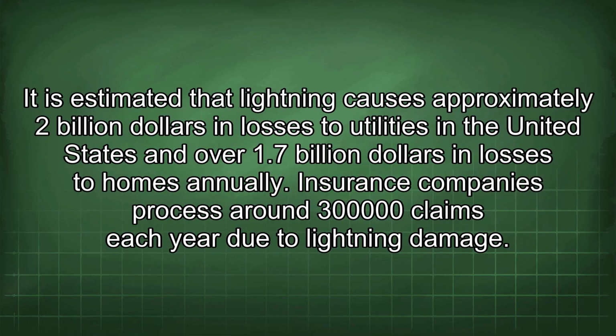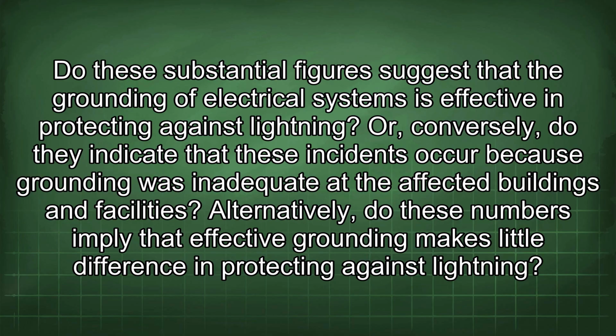It is estimated that lightning causes approximately $2 billion in losses to utilities in the United States and over $1.7 billion in losses to homes annually. Insurance companies process around 300,000 claims each year due to lightning damage. Do these substantial figures suggest that the grounding of electrical systems is effective in protecting against lightning? Or, conversely, do they indicate that these incidents occur because grounding was inadequate at the affected buildings and facilities? Alternatively, do these numbers imply that effective grounding makes little difference in protecting against lightning?